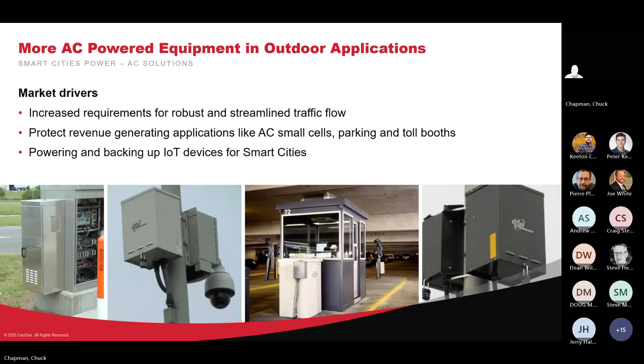So when you look at traffic and battery backup, there's the rugged power supplies, the FXMs attached to the alpha batteries in the cabinets, providing communications to know what's happening in that cabinet, not only at the power supply but maybe additional monitoring as well - monitoring the batteries, not only for their voltage or state of charge, but for their relative condition. There's an acceptance test we do that looks at the health of a battery over its lifetime.